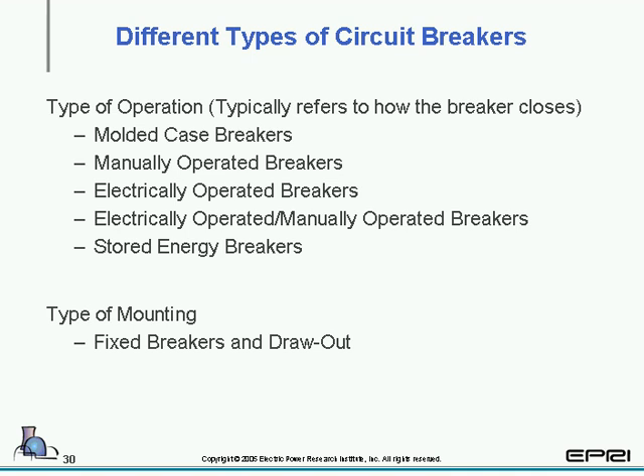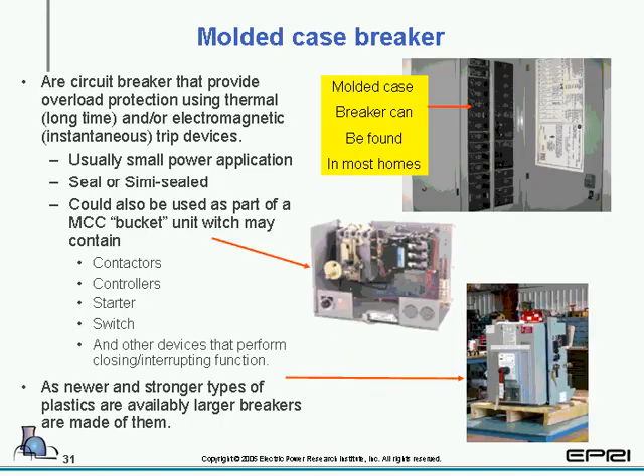The different types are molded case, manually operated, electrically operated, manually operated, and stored energy breakers. Then we'll be taking a look at the type of mounting. We have fixed breakers and we have draw-out breakers. Very first one, molded case. These breakers provide overcurrent protection using thermal and electromagnetic tripping devices.